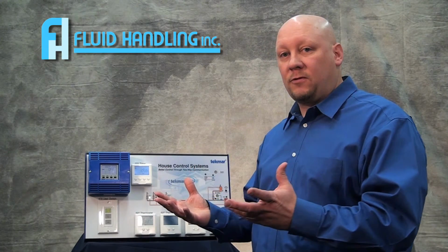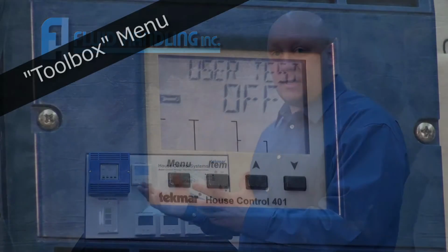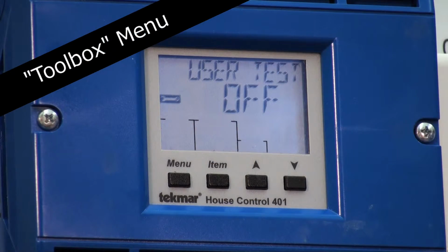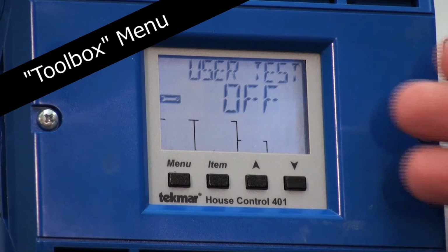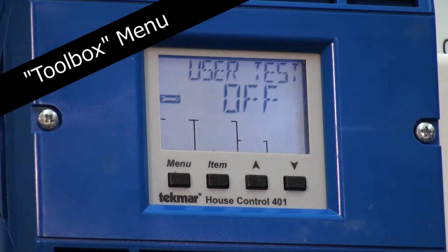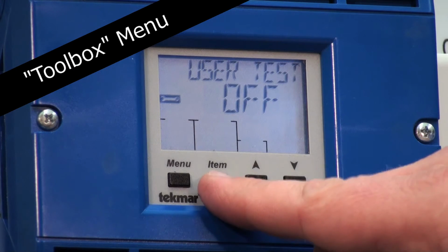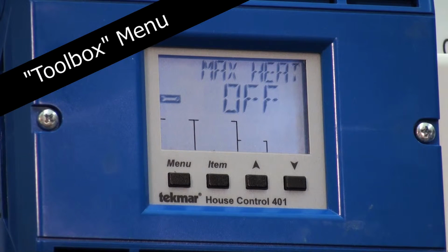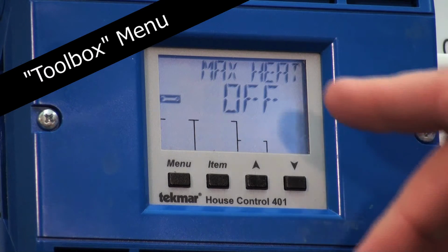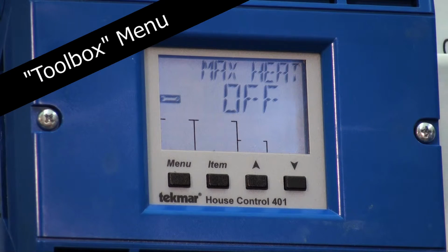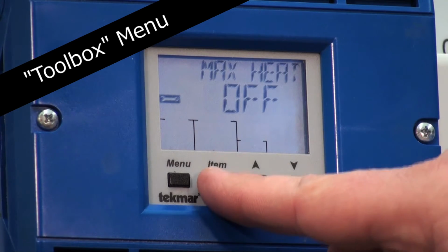If you are starting up the system, say you've had temporary heat in there in the wintertime, so it's hard to get a good run time to get the boiler to 100% fire, you can go in here, turn on the user test to on. The control will go through each individual relay and turn them on and off a few seconds at a time to make sure that everything is functioning. You can also max heat. Here's where if you want to know you want it running for 2 hours to get everything set up, you can set the max heat on here to 85 degrees and all thermostats. This unit will just run thinking it's trying to get to 85 degrees.